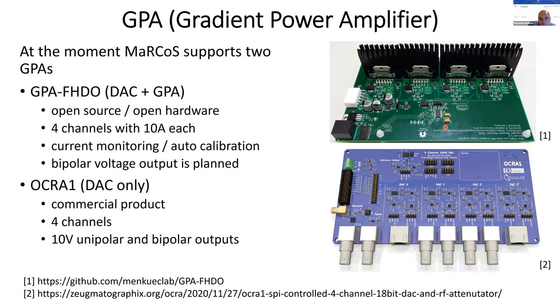This slide shows two gradient amplifiers that can be used with the Marcos system. On the top is the GPA FHDO — a gradient amplifier that also includes the DAC, making it a two-in-one. It's completely open source and open hardware, supports four channels at 10 amps each, and has current monitoring and auto-calibration. A bipolar voltage output is planned for the future. On the bottom is the OCRA1, which is DAC-only and partly open hardware, partly commercial, with four channels and unipolar and bipolar outputs.